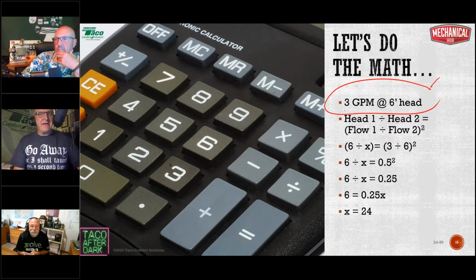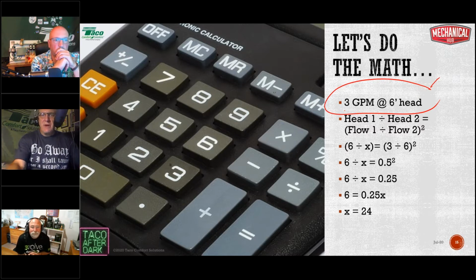So I know my head is 6 feet at 3 gallons a minute. Let's say I want to find out what my head is at 6 gallons a minute. You'd think if it's 6 feet of head at 3 gallons a minute, at 6 gallons a minute it should be 12 feet of head, right? Not necessarily. Let's put in the numbers we know: head 1 is 6, head 2 is X, flow 1 is 3, flow 2 is 6. So 6 divided by X equals 3 divided by 6, squared. 3 divided by 6 is 0.5, and 0.5 squared is 0.25. So 6 divided by X equals 0.25. Now we isolate for X: multiply both sides by X, so 6 equals 0.25X. To solve for X we divide both sides by 0.25, and we find that the head at 6 gallons a minute is 24 feet. So as flow goes up, head goes up exponentially, that's how it works.